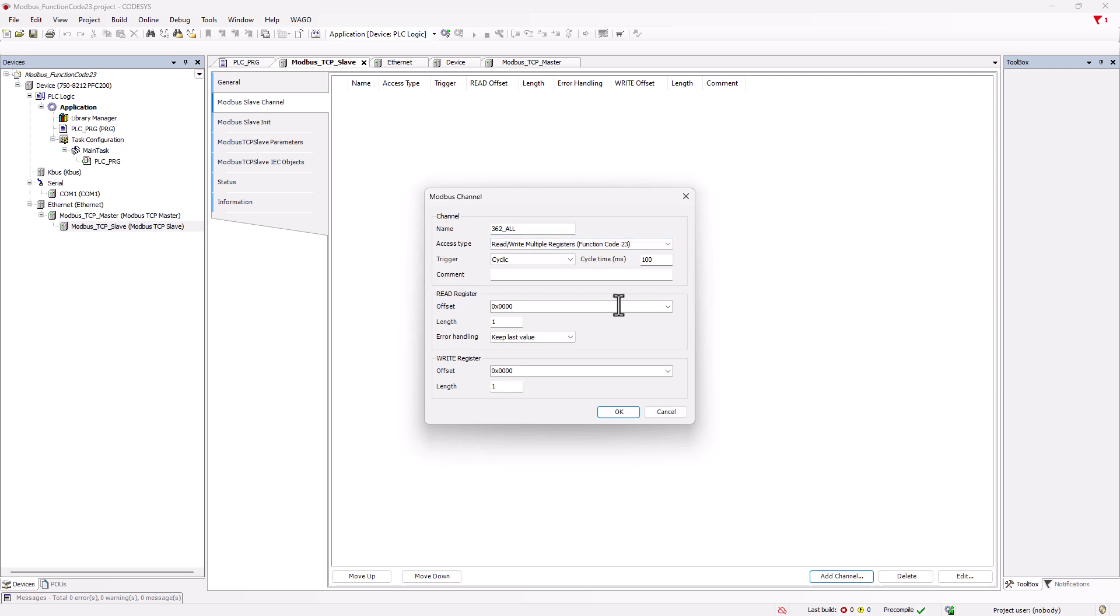For cycle time, we could now reduce the time since we only have one channel that is queried. 10 milliseconds is a popular value here. However, the bus task must also run correspondingly fast. If, as in this case, we let it run in the main task, we need to adjust the value accordingly. So, our Modbus connection runs as fast as the KBUS.